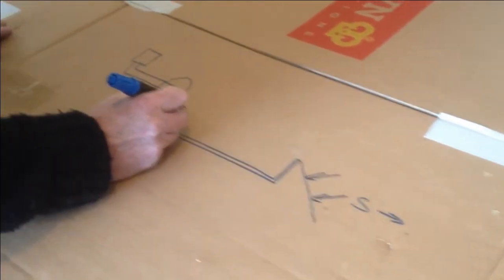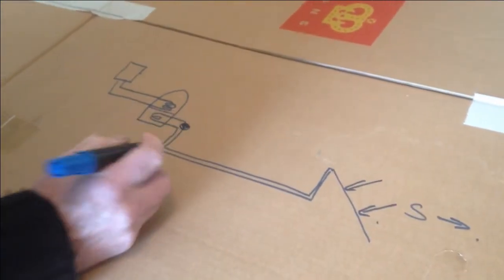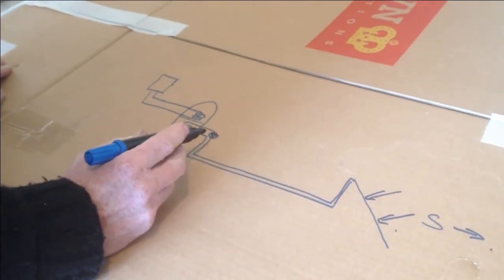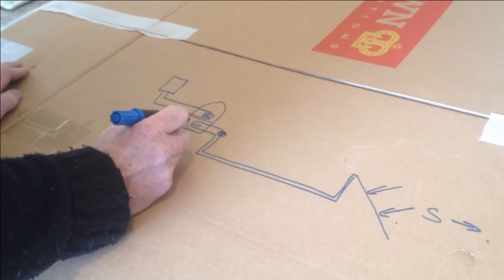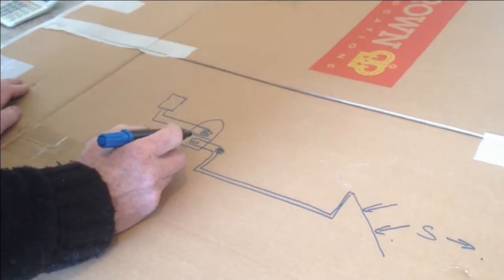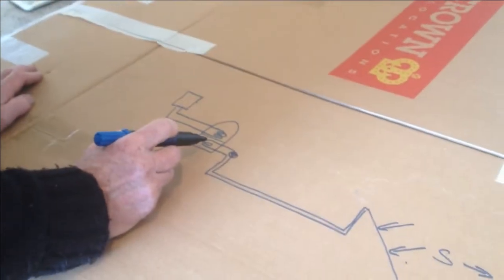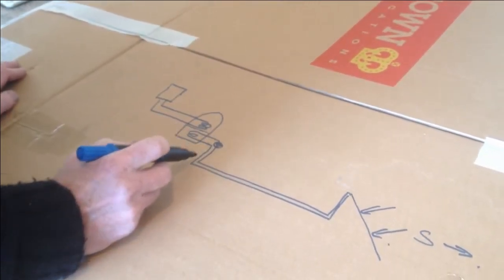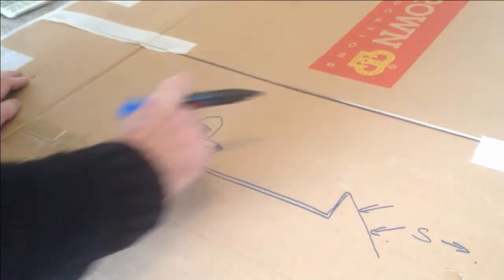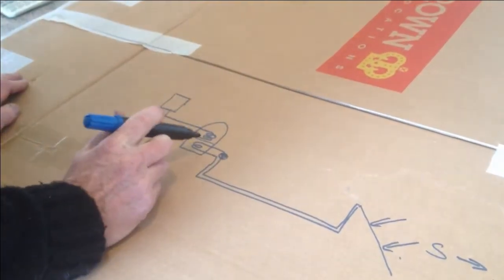We have a pump in the circuit to pump our solar fluid backwards and forwards. We don't have a check valve because what I've created is actually an anti-gravity loop so at night when the cylinder is hot it won't gravitate up to the panel. If the panel was up here it wouldn't gravitate up to the panel and lose heat.